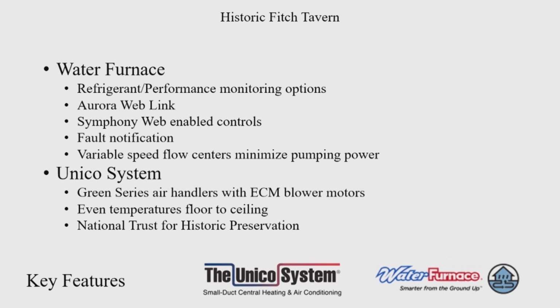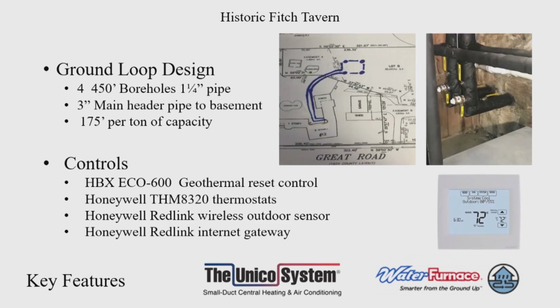We use variable speed flow centers on everything so that we can minimize that pumping power. Also, the high velocity systems from Unico uses the Green Series air handlers. Those all have ECM motors, again, to reduce electrical consumption in the home and give even temperatures throughout the space. And one of the other benefits is Unico is listed with the National Trust for Historic Preservation to be used in old homes.